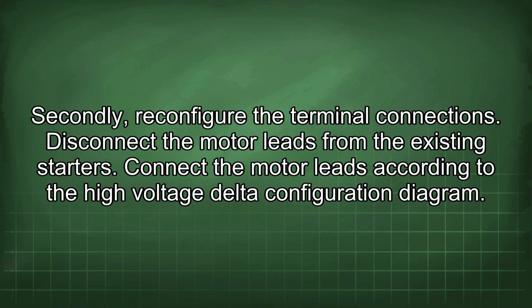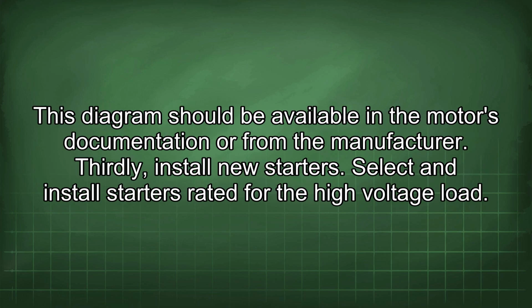Secondly, reconfigure the terminal connections. Disconnect the motor leads from the existing starters. Connect the motor leads according to the high voltage delta configuration diagram. This diagram should be available in the motor's documentation or from the manufacturer.